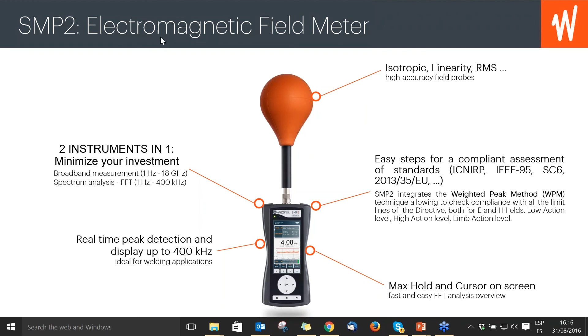This unit, the SMP2, also permits to have a time assessment. It means comparing the result to a limit. There are several limits depending on the normative that you will follow. In the States, for example, you have to compare to the IEEE 95 or to ICNIRP, but also in other countries like in Canada, you have to compare to safety codes, in Europe to the 2013 directive, etc. And the SMP2 uses the weighted peak method, which is the most precise technique, allowing to check compliance with all the limits for both electric and magnetic fields.